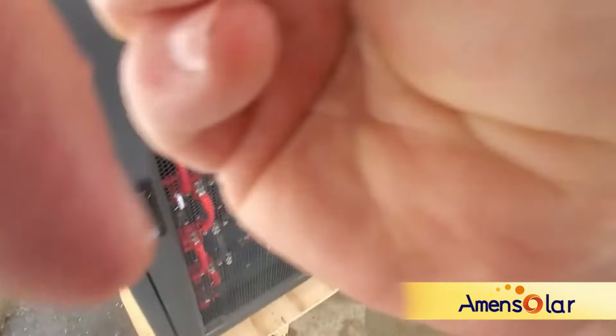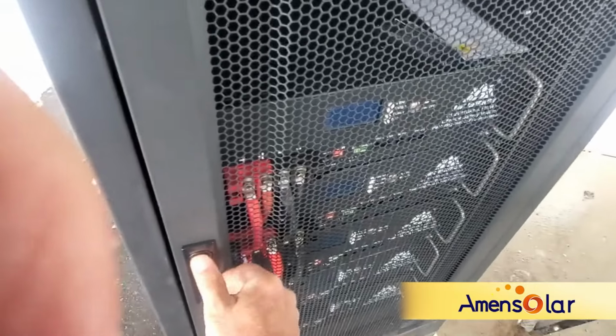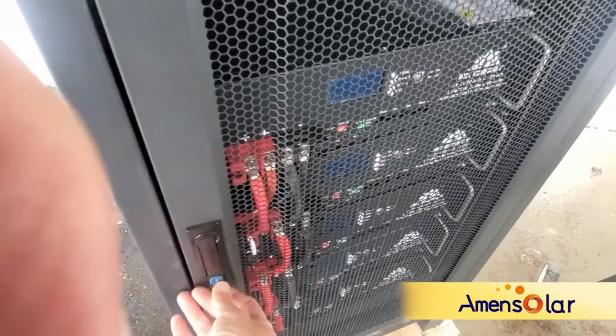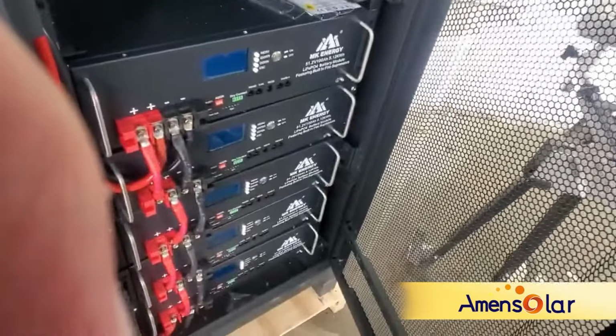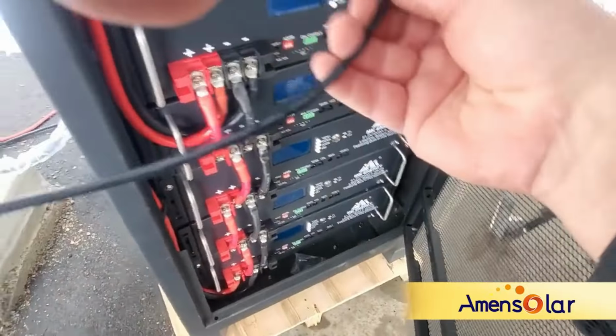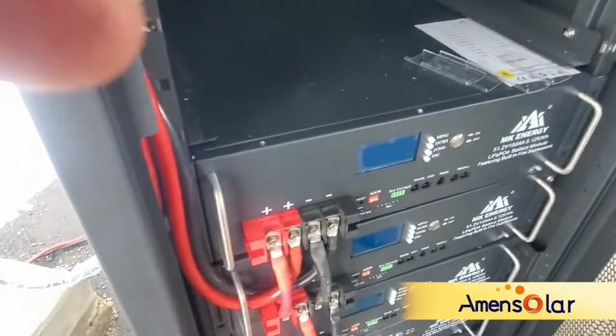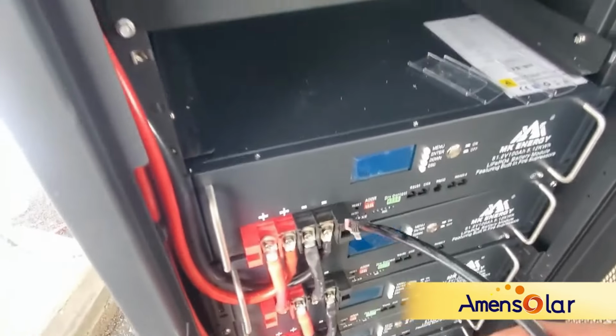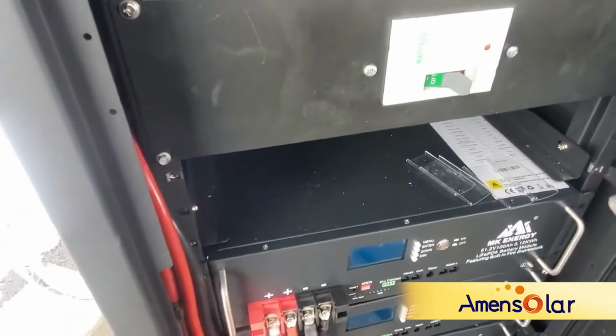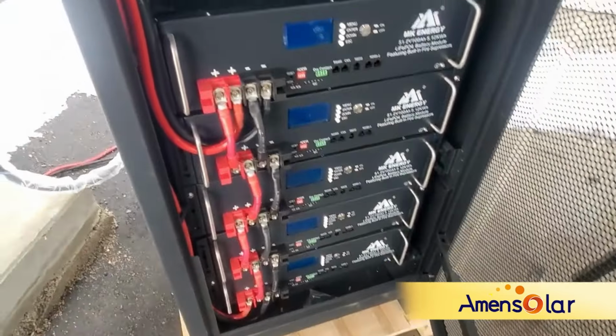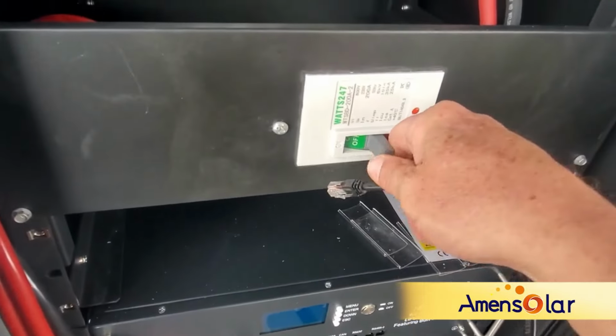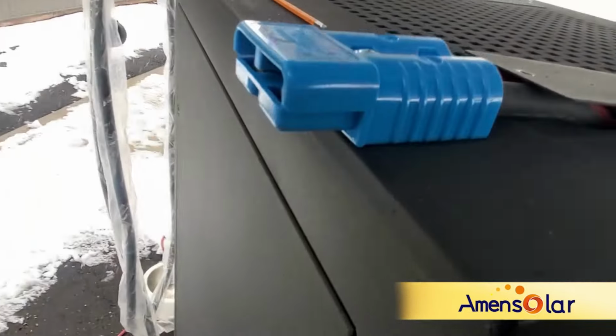So I'm going to click save, that's how we click save. I'm going to plug this into, and you'll notice our lithium battery set, we don't have any communication wires between them, so we're just going to have one battery do the communication right now. These batteries aren't connected to the output at all, just a little plug. This is our battery rack, with a 200 amp breaker built in, and it comes out on an Anderson plug on the side. So this is not even connected.